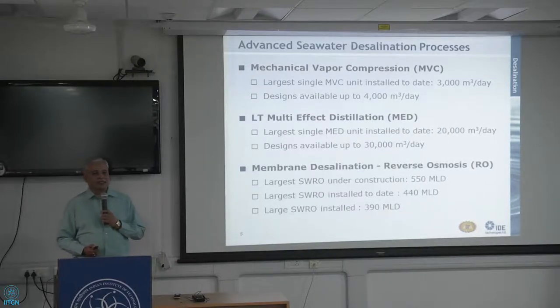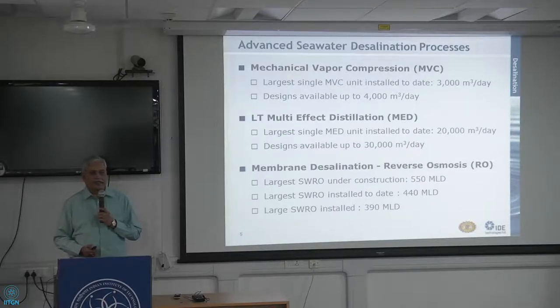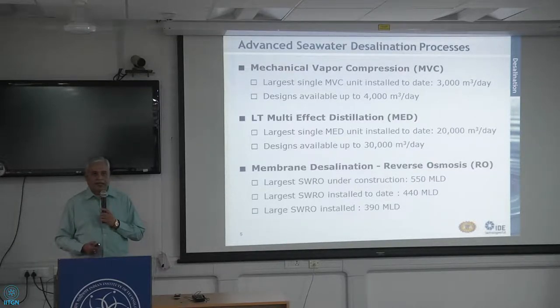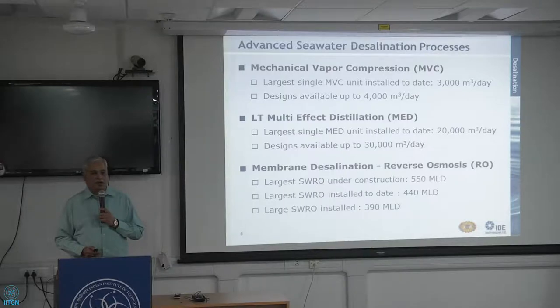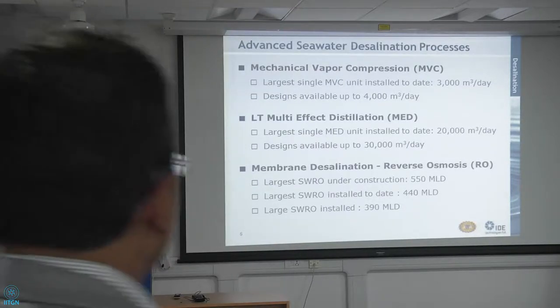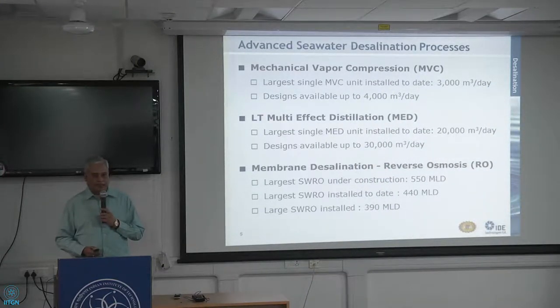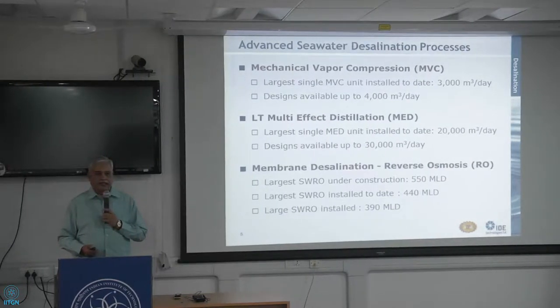The three advanced desalination technologies currently available for large-scale desalination are: first, mechanical vapor compression — a thermal desalination technology that utilizes electrical power as the energy source. Any desalination process does require some source of energy to remove salts from saline water. The second technology is multiple effect distillation, a more refined process over multistage flash — multistage flash is essentially outdated today, and most projects have switched to MED because it is a low temperature distillation process. The third technology is reverse osmosis, a membrane technology that removes salts down to the ionic level through a filtration mechanism.